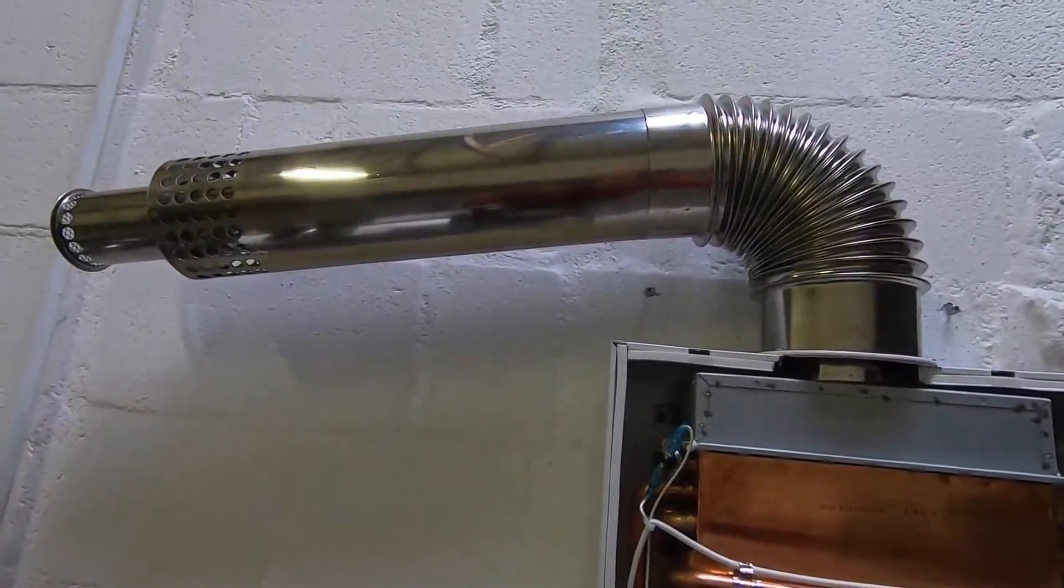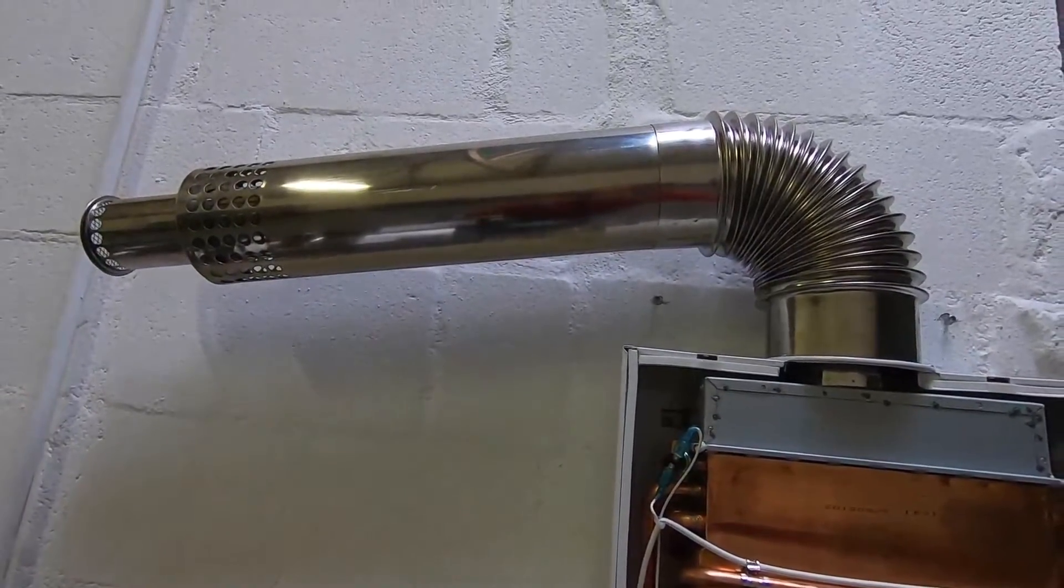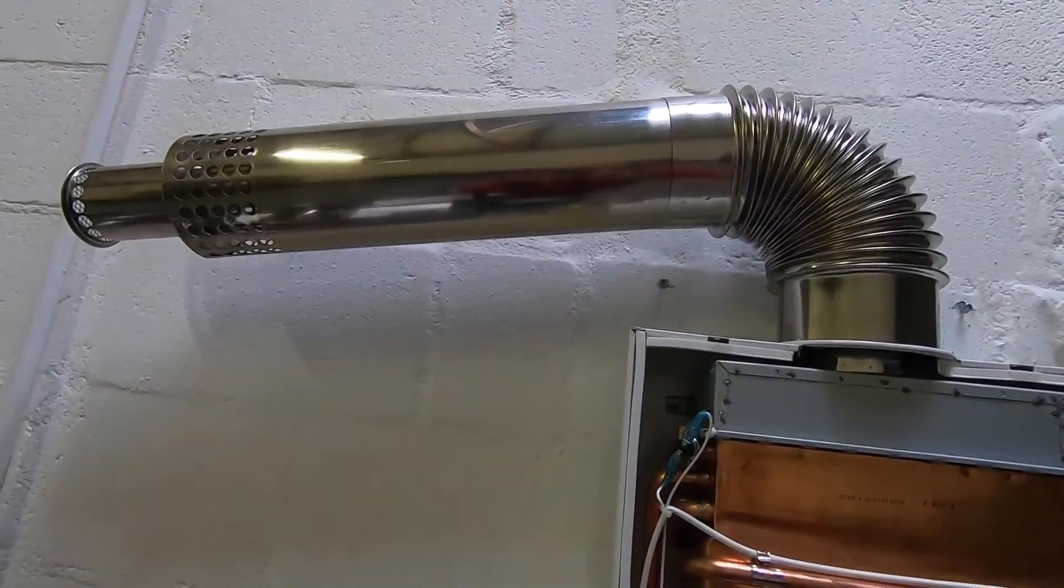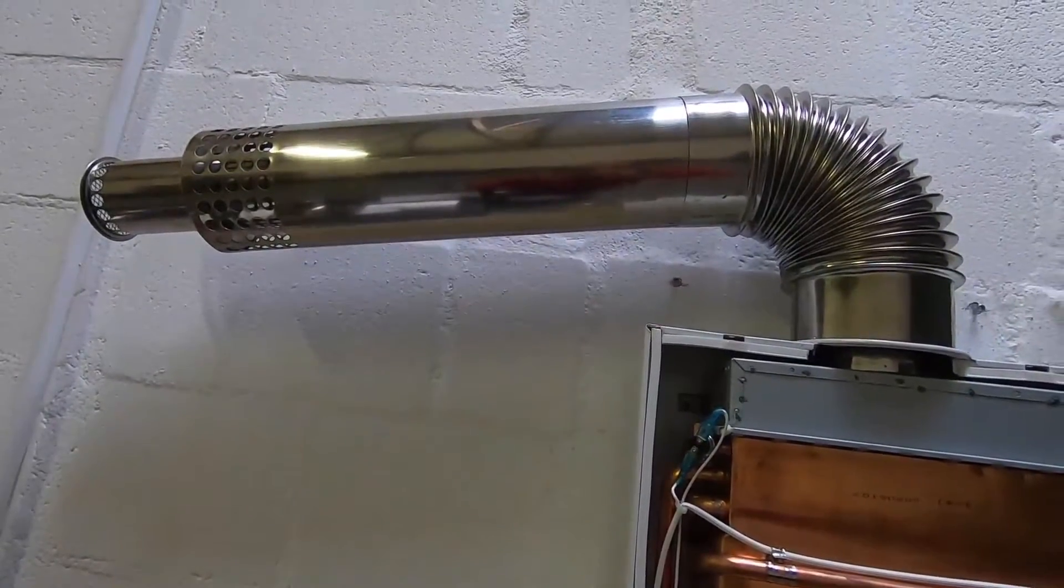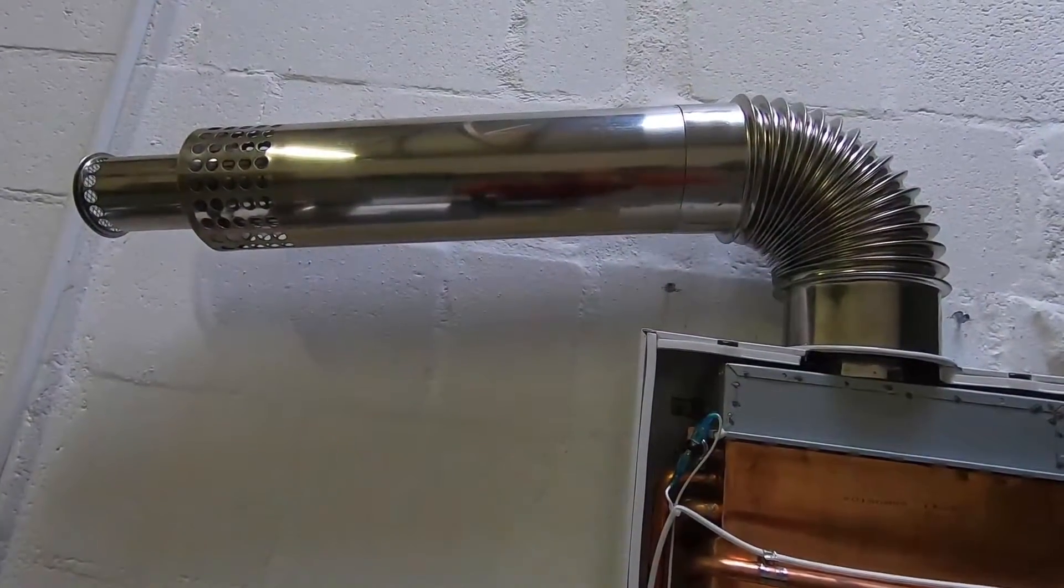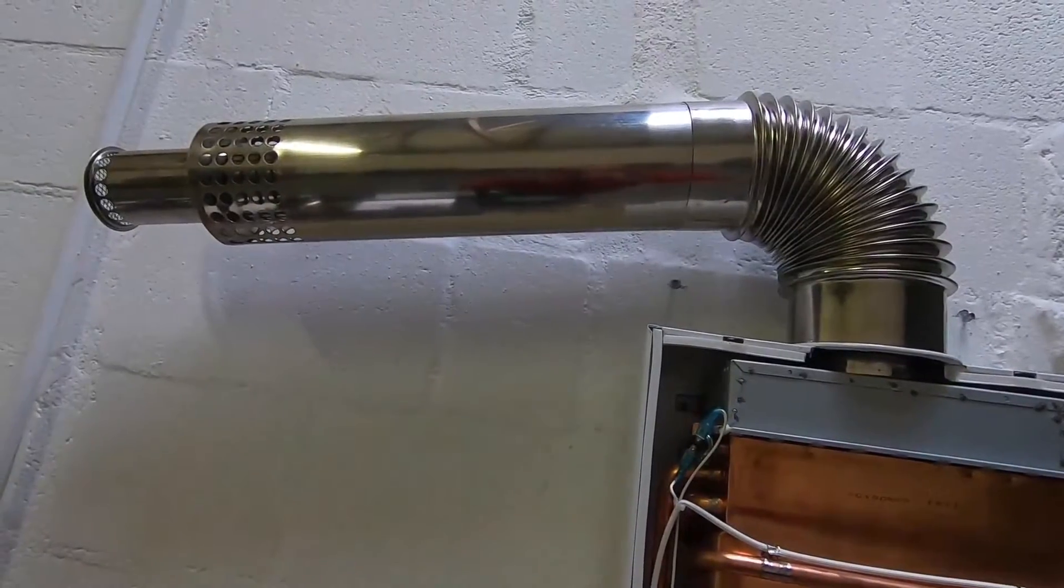You will notice that the flue has a slight downward pitch and this is to prevent any condensation from dripping back into the geyser. The condensation is caused by the difference in temperature between the inner flue and the outer flue.